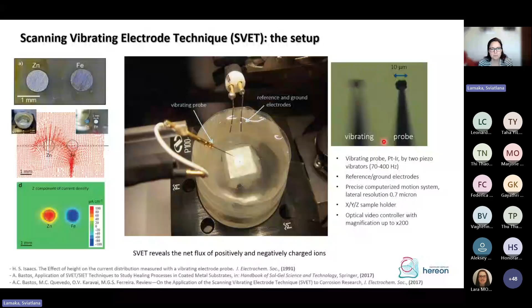So before we perform the current calibration, this is a typical view of the calibration setup. This is the vibrating probe of SVET approached to a fixed distance, normally 150 micrometers, to a point current source. In this case, it's a glass capillary, and we inject a positive current of 60 nanoampere. Before we perform this current calibration, we also calibrate the geometry of the probe vibration to make sure that there is only vertical or only horizontal vibration, so this probe vibrates in 2 planes.